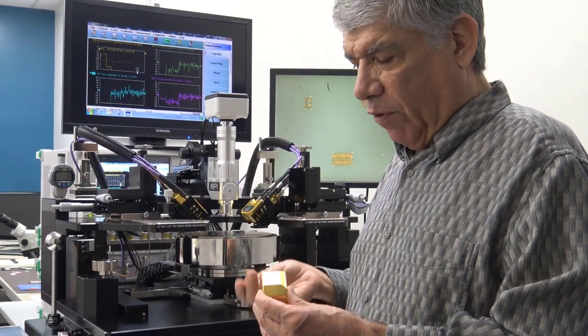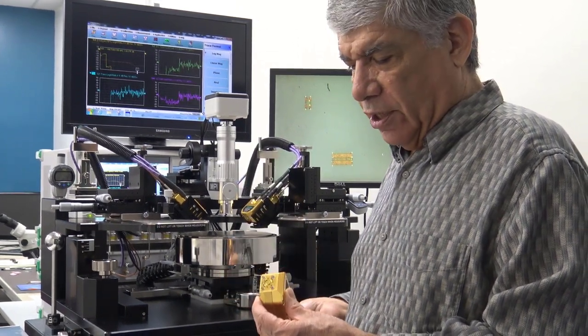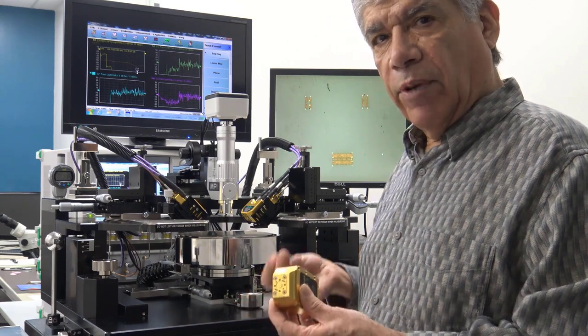The threads we found can wear and create some alignment issues after a period of time. And we're finding that the flange approach is providing much more repeatability.